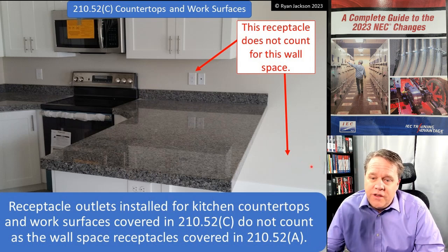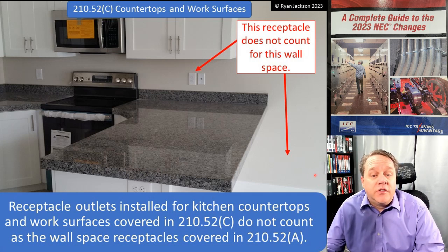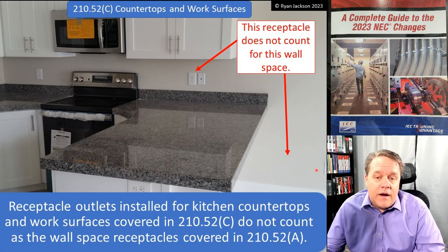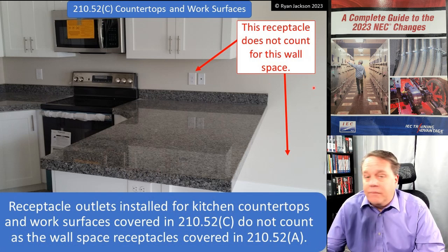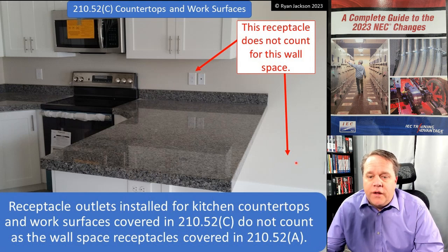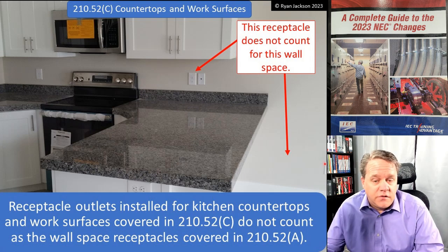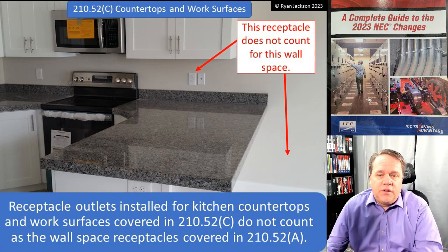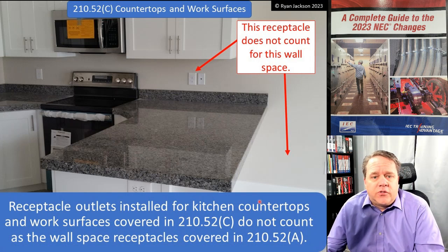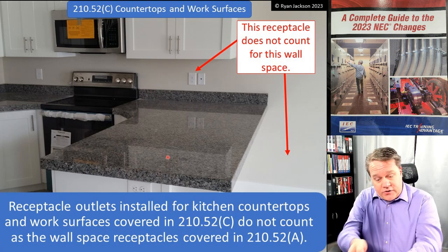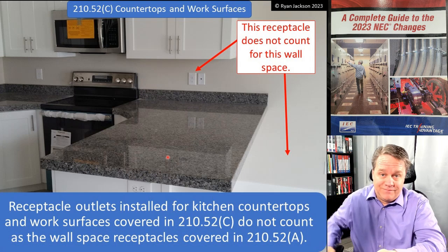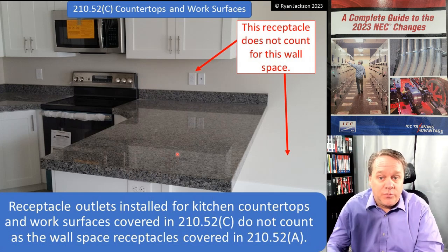Countertop receptacles do not replace wall-space receptacles. In this dining room photo, there is a wall-space receptacle at the edge — without it, you could not substitute the countertop receptacle to satisfy the wall-space layout. The reason for this rule is largely due to peninsula receptacles: a receptacle at the peninsula facing outward should not count as the wall-space receptacle behind the person standing at it. That's why these two types do not intermix.